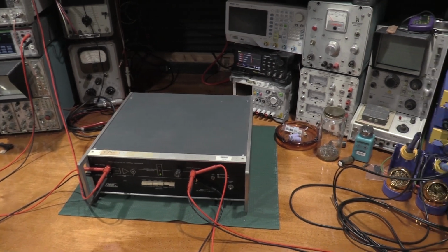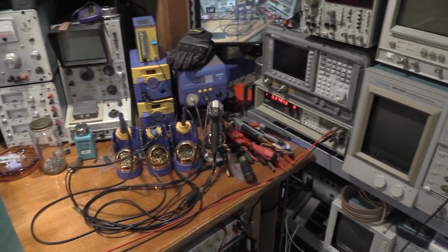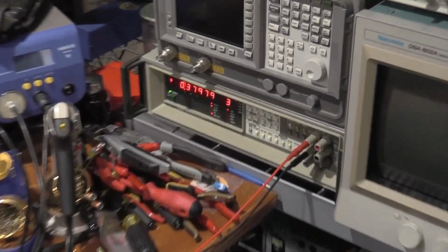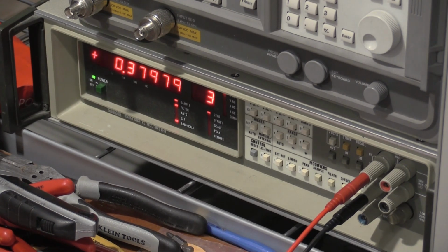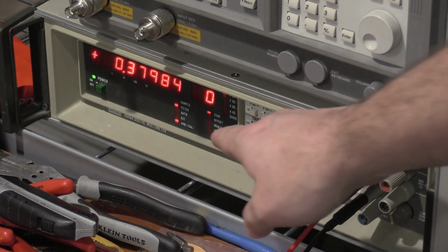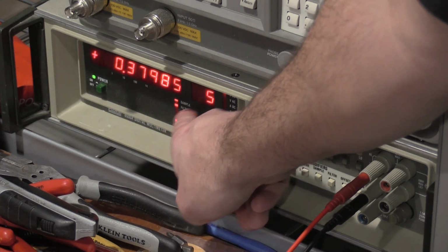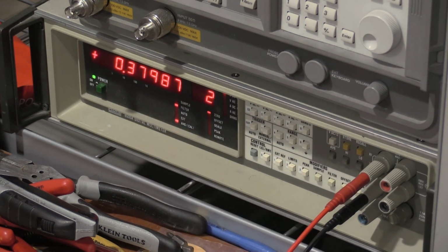Taking a look at over here real quick, though. We have this meter right here. We'll zoom in. This is measuring the compliance voltage across the current shunt in the 7500 or 7510. This is set in 6.5 digit mode. This is typically a 5.5 digit meter. However, with sampling, filtering, and averaging turned on, it will add a 6 digit and be a 6.5 digit meter, but only on the 10 volt scale. That's just a limitation of that particular meter.